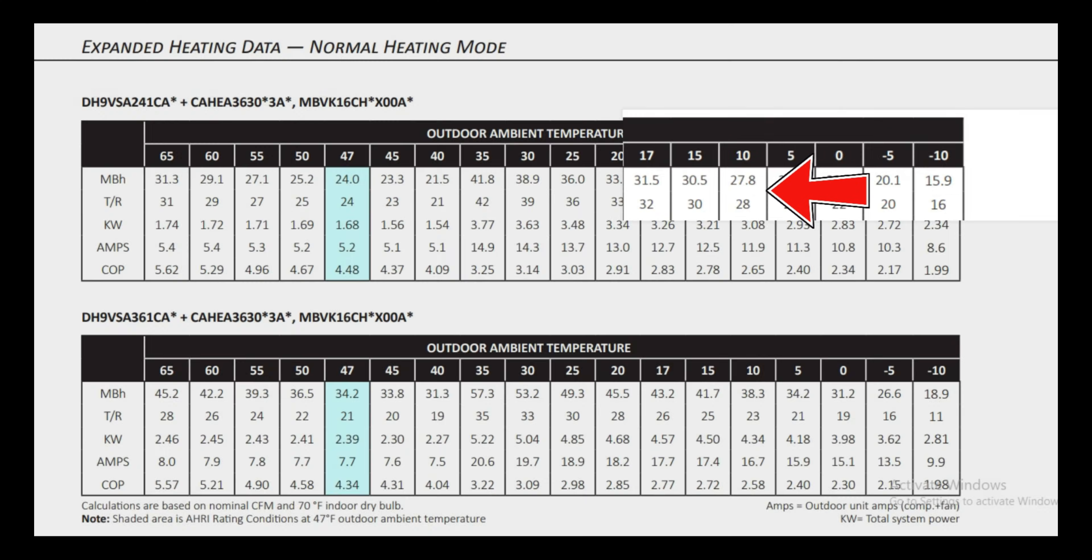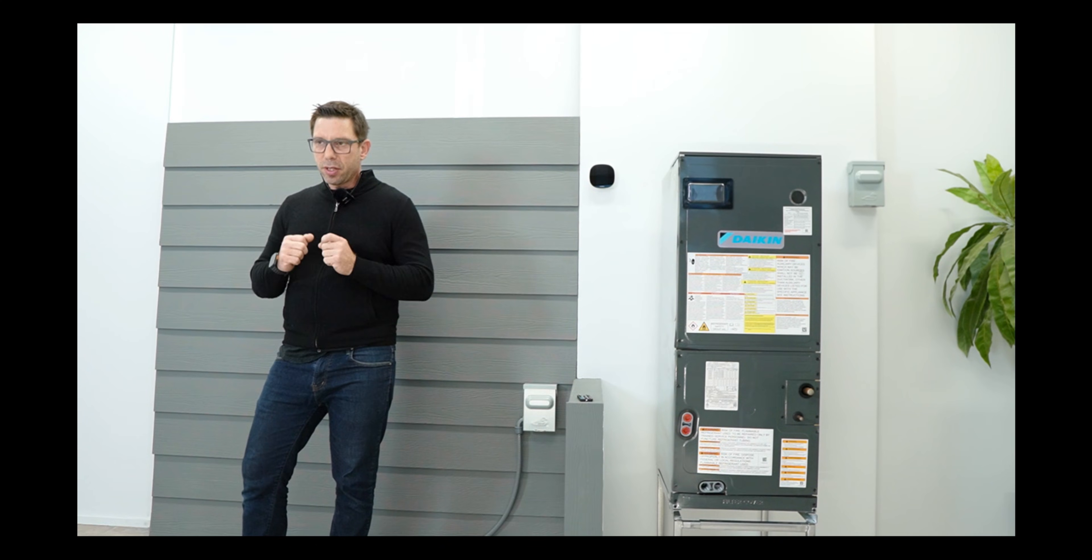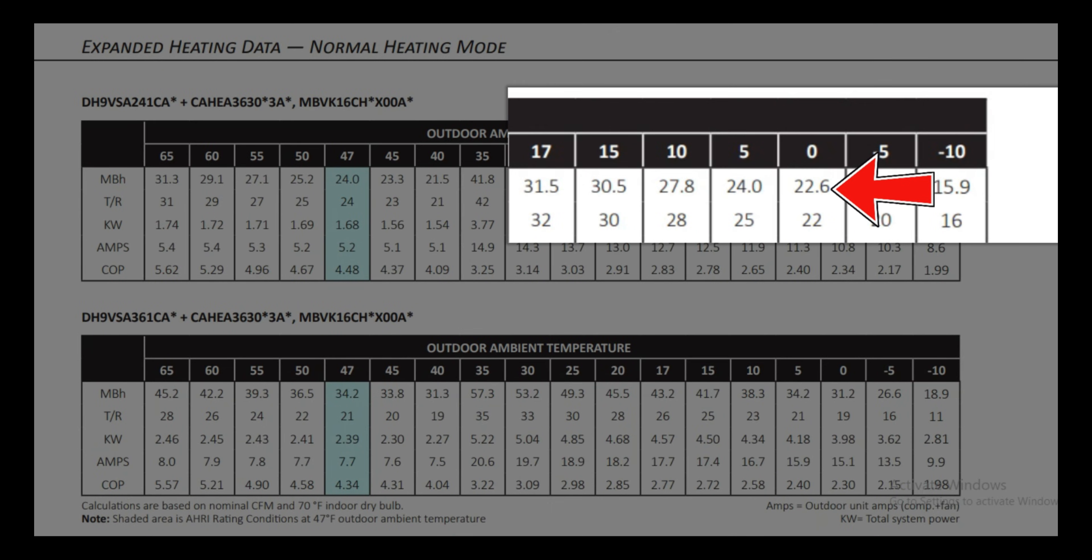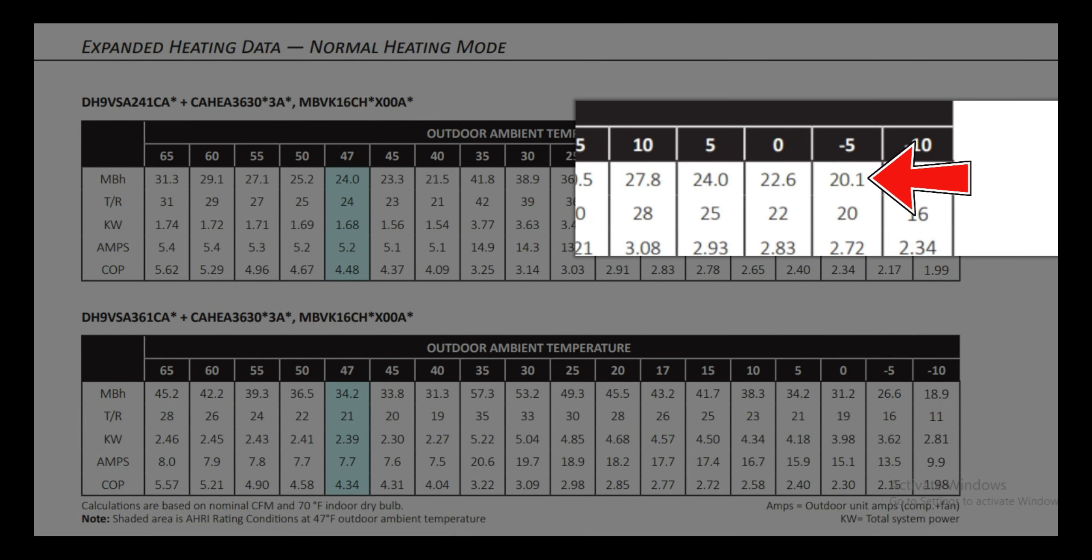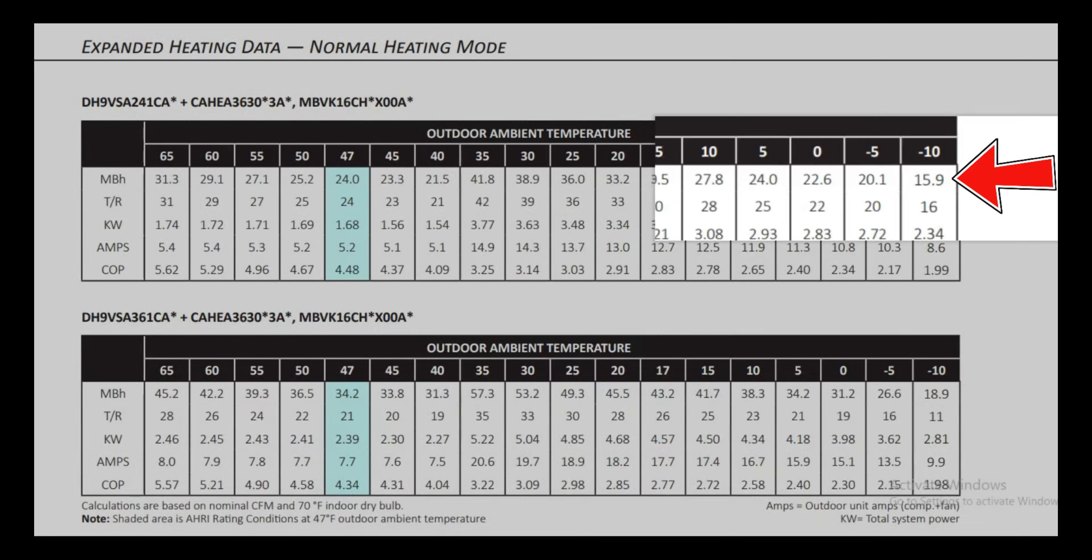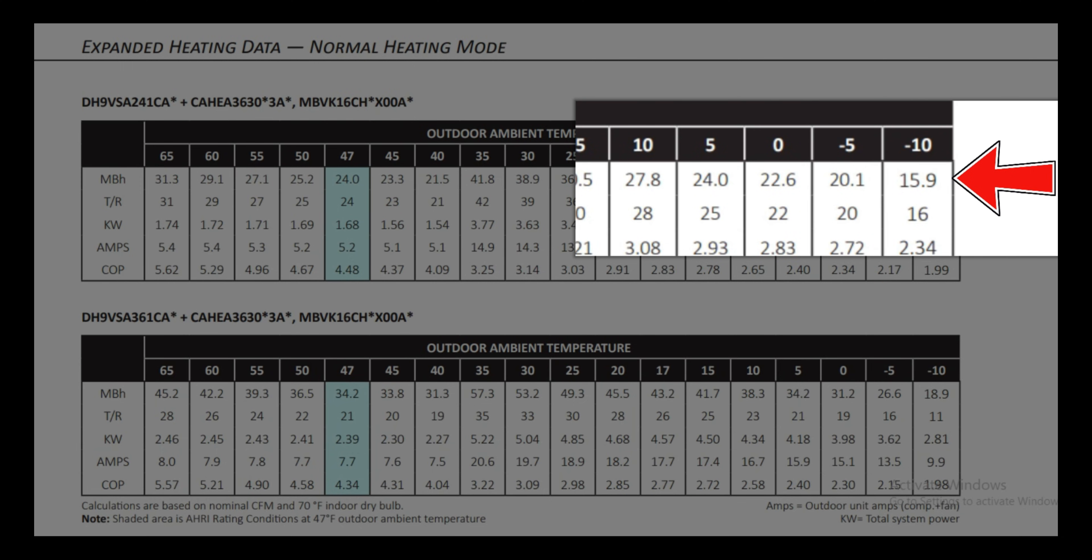At 5 degrees Fahrenheit, the system continued to deliver its full nominal heating capacity. At zero degrees, it falls just below two tons. At minus 5 degrees Fahrenheit, it drops below two tons, but still remains over one and a half ton at 20,000 BTUs. At minus 10 degrees Fahrenheit, it still produces just below one and a half ton of heating power. Unbelievable. And these systems just appeared on the market. The future looks absolutely amazing. But the question remains the same: do you really need a dual fuel system? Or will this Aurora system provide adequate heat? Keep watching and you'll find out.